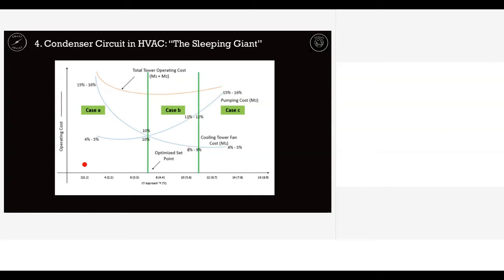So we had data from 5 to 10 to 15 sites, and there's actually a lot of data coming through, and we came to know that we need not operate the condenser pump and cooling tower in a constant fashion. We actually used this data to run both of them in a variable way. So if the cooling tower approach is low, then the condenser pump should be kept at lower frequency and the CT fan should be at higher frequency.